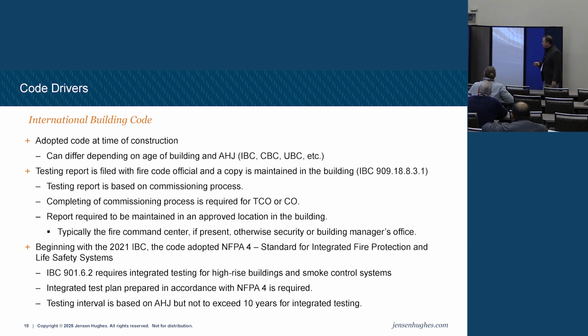Beginning in 2021, the IBC now requires NFPA 4 compliance. NFPA 4 is a standard for integrated fire protection and life safety systems. So in other words, when I'm testing, it's pretty common for contractors to say, look, normally when we do this, it'll trip these three air handlers, but we're going to bypass that and just show you the sequence of operations. NFPA 4 says no. If you test this system and it interacts with these three, we have to see those three activate.